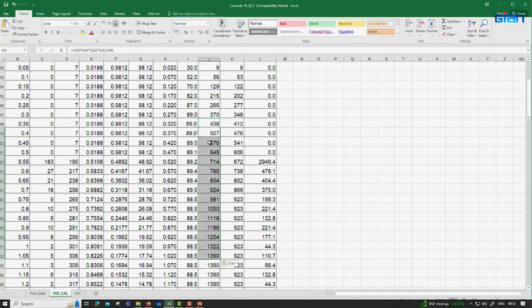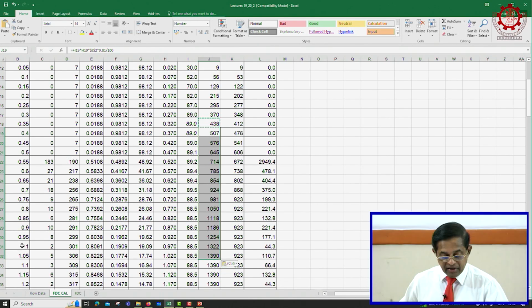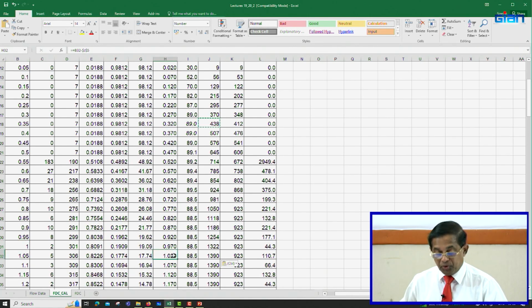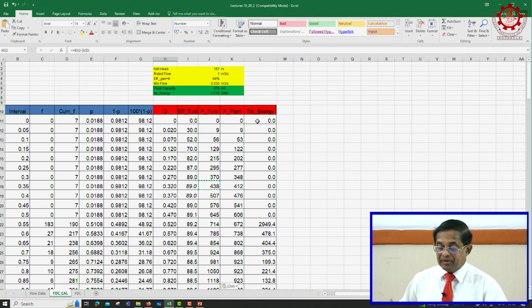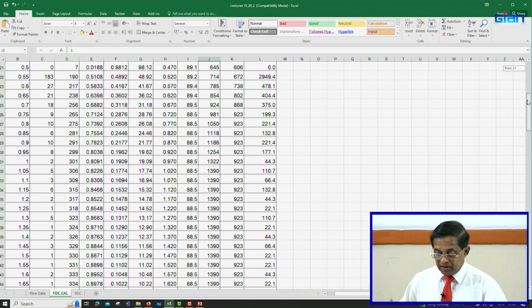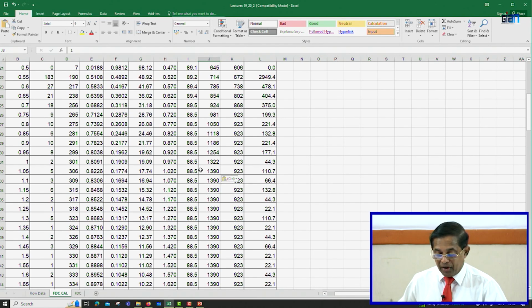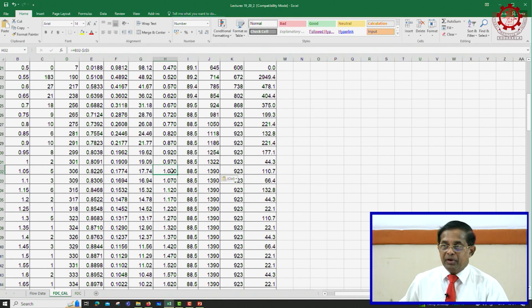We go on like that, but you can see the flow is becoming 1 here. After deducting the environmental flow, 1.02, we will virtually take it as 1. So, we have taken the rated flow for this example as 1 cubic meter per second, that is from our economic calculation. At rated flow, 1.02, almost 1 here, we are designing the plant for that. So, we cannot have higher capacity than that, because we have decided to have only 1 cubic meter per second as the rated flow.